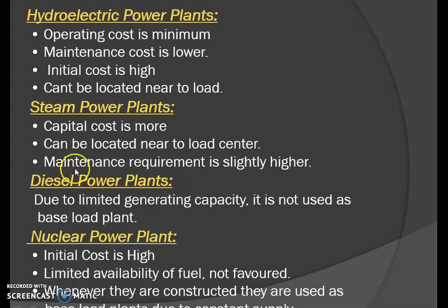Now the various different types of power plants. For hydroelectric power plants, the operating cost is minimum and the maintenance cost is lower. Operating cost is minimum because the fuel generally used here is water, which is generally available from nature. Maintenance cost is lower. Initial cost is high because the capital cost involved in the hydroelectric power plant is very high. It can't be located near the load center because lots of land is required for its dams, reservoirs and tailrace. Now for the steam power plants, capital cost is more, they can be located near the load center, and the maintenance requirement is slightly higher.